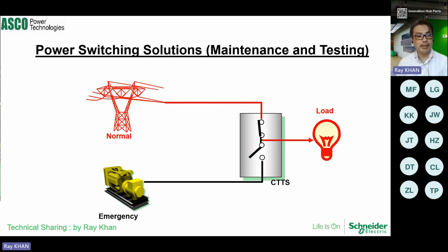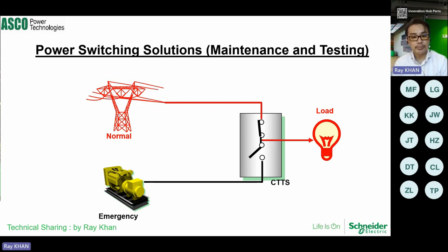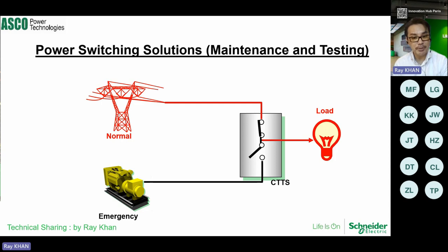Next, regarding the maintenance aspect: projects like data centers or airports may require ATS testing every few weeks. The issue is that testing affects the actual load. With closed transition, a make-before-break occurs between 40 to 70 milliseconds. The generator starts, power between the two sources is ensured, then the make-before-break transfer occurs with minimal interruption. Using an ATS is much more preferred even for maintenance aspects compared to using three circuit breakers for make-before-break. Gensets are normally tested on a monthly basis.